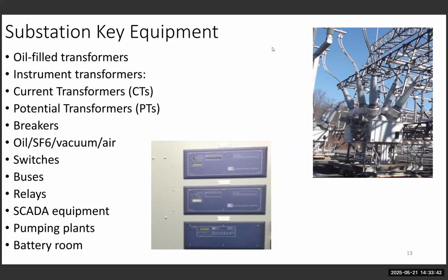Great job. There's another transformer type known as instrument transformer. So we mentioned SCADA before, but imagine you have a massive transmission line. Do you just throw a plug and run a meter? The answer is no. You basically put something called instrument transformer. There's two of them, the CT and PT. CT is current transformer, PT is potential transformer. So they basically step down the very, very high current magnitude and the very, very high voltage magnitude to a much lower level that we could use. For example, it could be 2000 amps and you only get like half an amp.